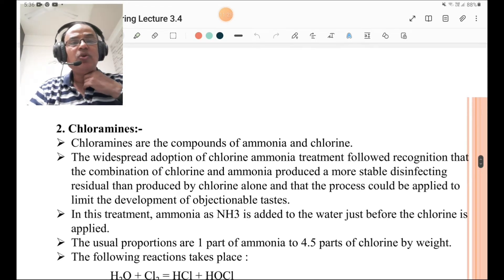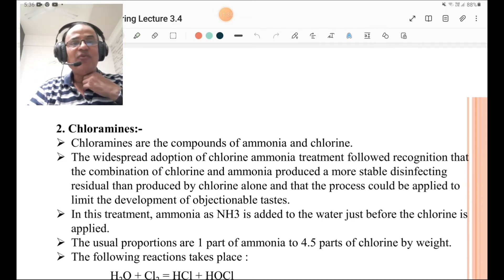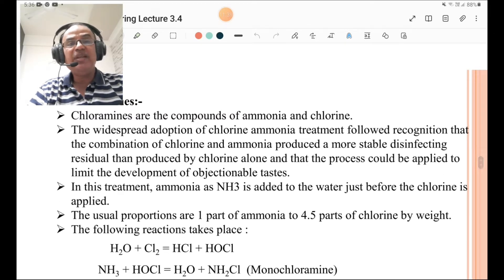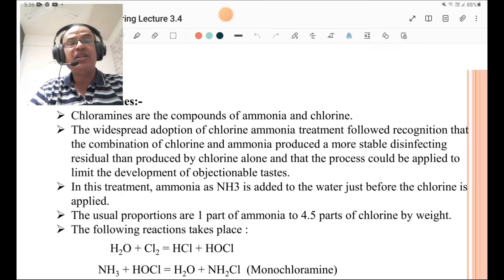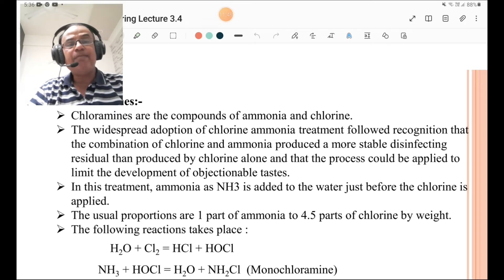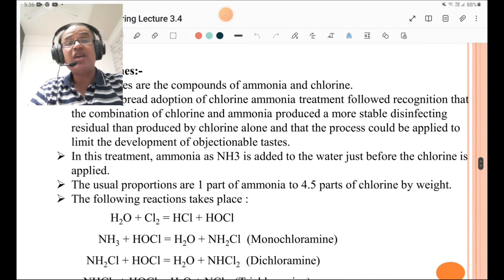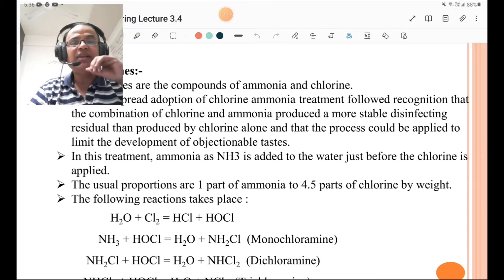The second form is chloramines. Chloramines are compounds of ammonia and chlorine. The widespread adoption of chlorine-ammonia treatment followed recognition that the combination of chlorine and ammonia produced a more stable disinfecting residual than chlorine alone, and that the process could be applied to limit the development of objectionable tastes. In this treatment, ammonia as NH₃ is added to the water just before chlorine is applied — first ammonia, then chlorine.